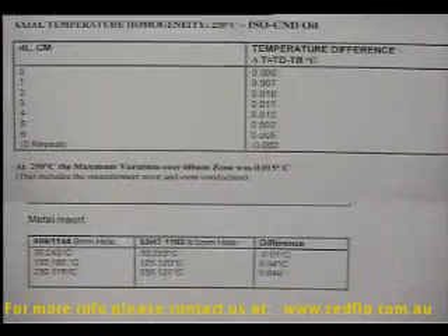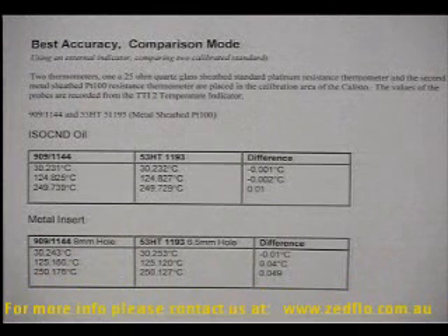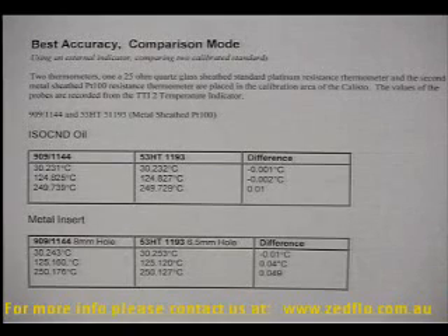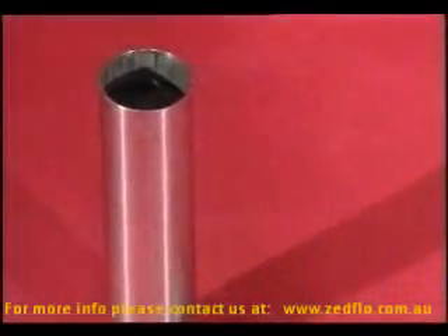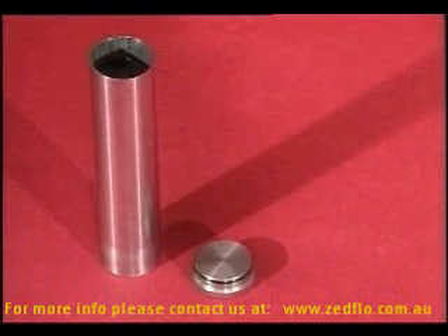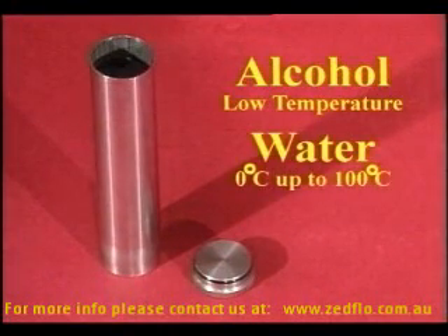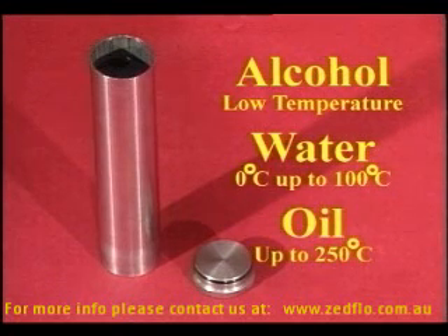And if you look again at the best accuracies we can achieve from a metal insert versus an oil within the stirred liquid container, we can see that the figures are about 5 times better for the oil bath than the metal block bath. So not only can we calibrate odd and short-shaped sensors, we also reduce the uncertainties by about 5 times. The little stirred liquid bath can be filled with alcohol for low temperatures, water for temperatures between 0 and 100 degrees Celsius, or oil for temperatures right up to 250 degrees Celsius.